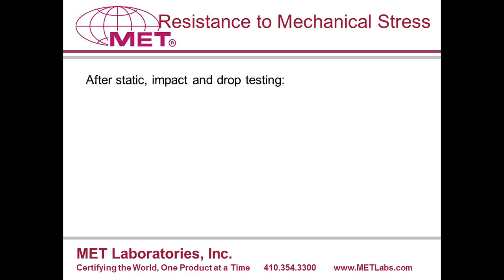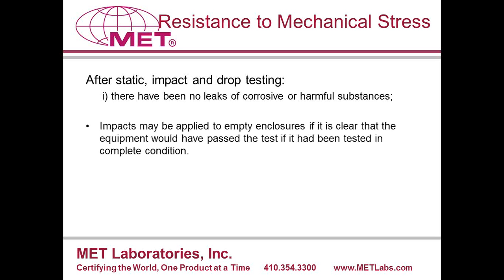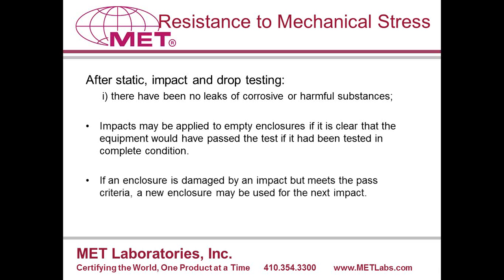The criteria for mechanical stress testing has been somewhat expanded to include hazards associated with corrosive or harmful substances. Two things have changed in how to perform the test. The enclosure can now be empty during the test, and if an enclosure is damaged or cracked during the test, but not to the extent where the enclosure fails, a new enclosure can be used for the next impact.